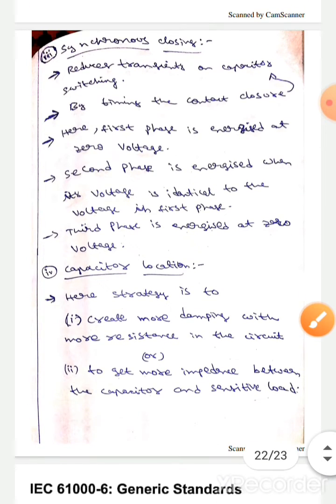The next one is capacitor location. Here strategy is to create more damping with more resistance on the circuit, and to get more impedance between the capacitor and the sensitive load.